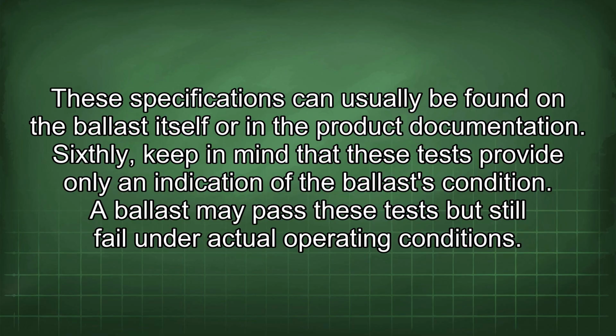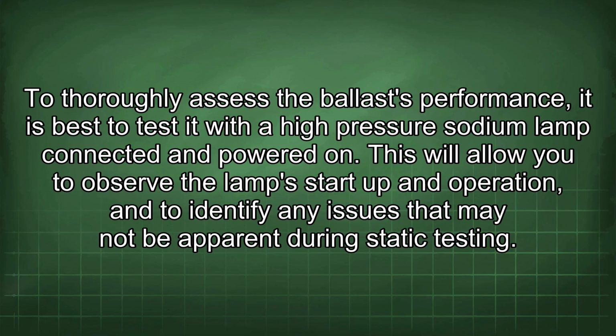Sixthly, keep in mind that these tests provide only an indication of the ballast condition. A ballast may pass these tests, but still fail under actual operating conditions. To thoroughly assess the ballast's performance, it is best to test it with a high-pressure sodium lamp connected and powered on. This will allow you to observe the lamp's startup and operation, and to identify any issues that may not be apparent during static testing.